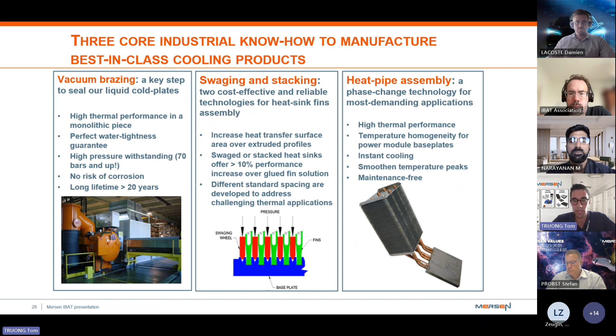On the right side, we still have our air cooling technology, but you will notice that in the middle of it, we have heat pipes that allow us to spread the calories along the complete cooling. So it allows a better thermal performance in comparison with standard air cooling, and a temperature homogeneity. Thanks to the heat pipe, it smoothens the temperature peaks, and it's maintenance-free.